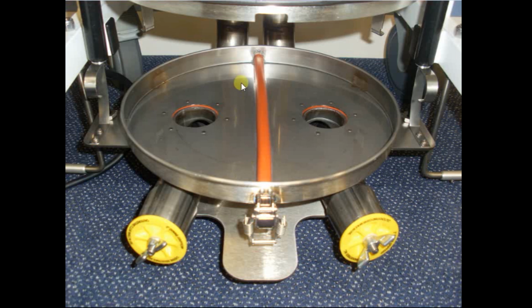So as you can see, what we have now, remember from the front we had the valve block and the descending corrugated tubes going down. This is the inspiratory side, this is the expiratory side. So gas is going to return from here, come in here, come up through this hole into the bottom of the soda lime tray. And the soda lime tray itself is split, so it'll go through this side of the tray first, up over the top, and then down through the soda lime on the inspiratory side, through this aperture, and then up the tube and back to the patient circuit.